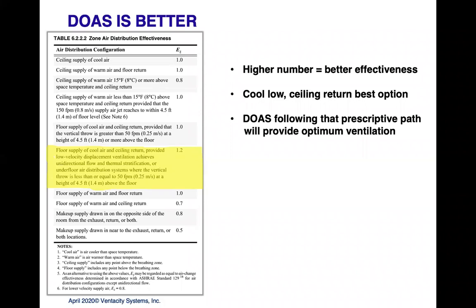So what you'll see there is a floor supply of cool air and ceiling return. Typically what that means is cool air coming in low, and people, computers, all the waste heat that's generated inside the space, or solar, warms that air a little bit, and it rises and then goes to exhaust out of the ceiling. That is the optimum that you can do. Bring it in low, exhaust it high, and bring it in low a little bit cooler. That is the best way to ventilate spaces. So if you really want to design to be the healthiest possible, that's the way to do it.